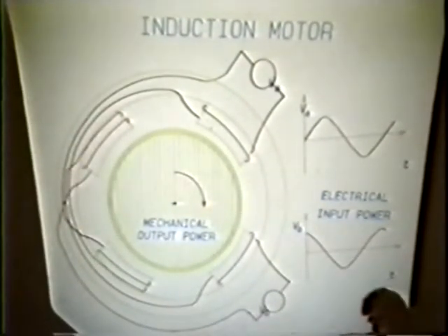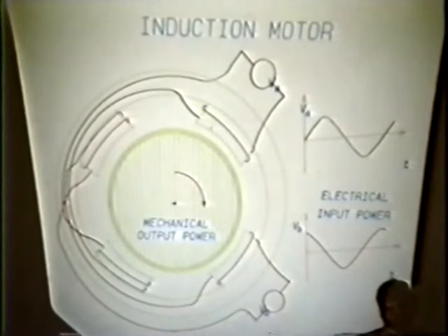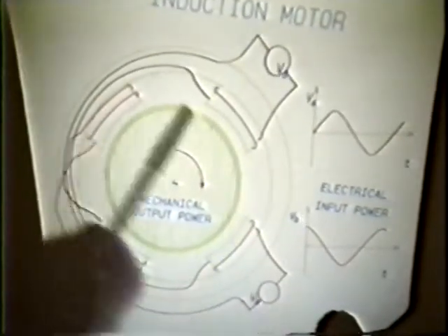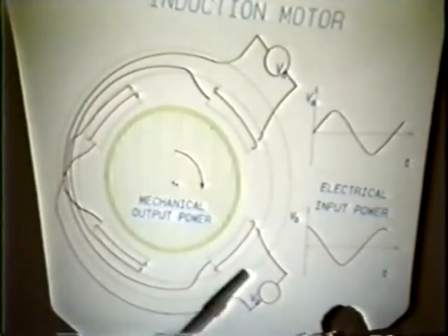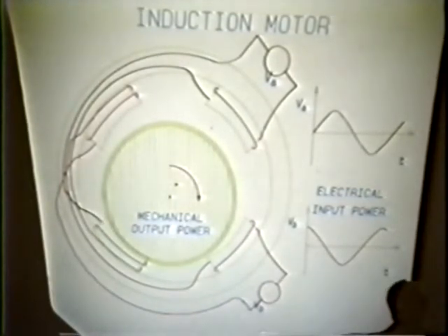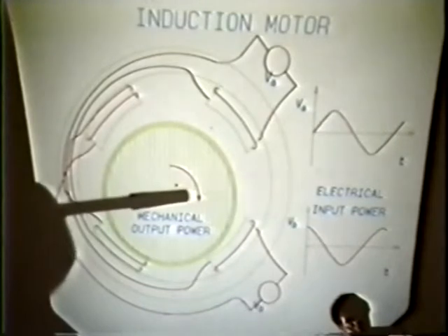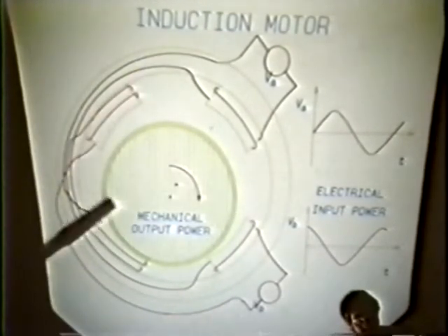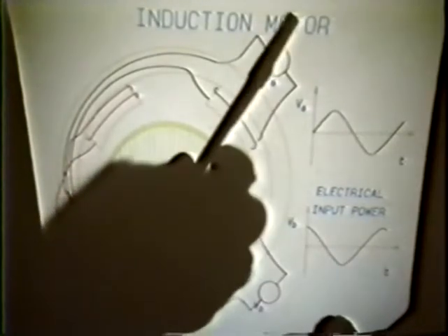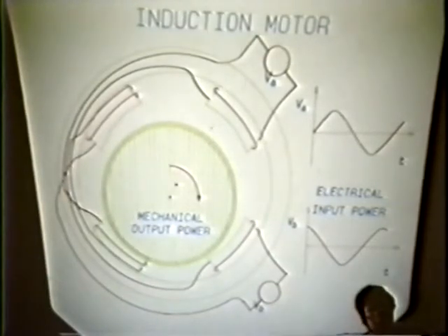Basically use any piece, metal piece, which conducts the current, and generate basically shorted turns on the secondary. So this will look like a two-phase transformer with the primary windings, and this will be secondary windings of that two-phase transformer. And through the transformer action, the current is induced in the secondary winding, and because it's shorted, voltage is induced. And because it's a shorted turn, tremendous current is introduced, and a rotating field in the stator creates also the corresponding rotating field in the rotor.